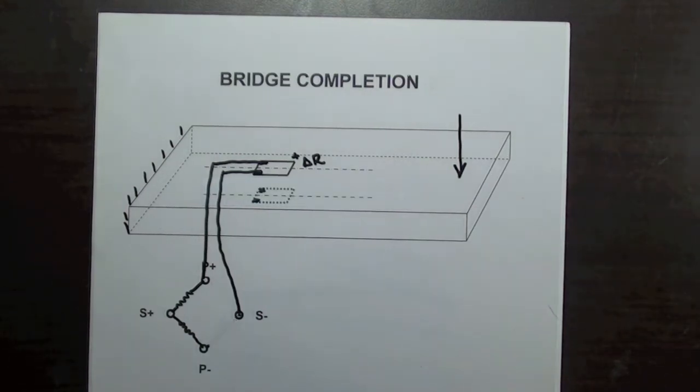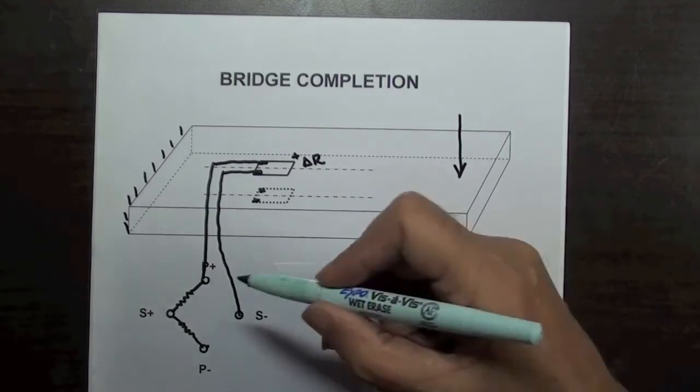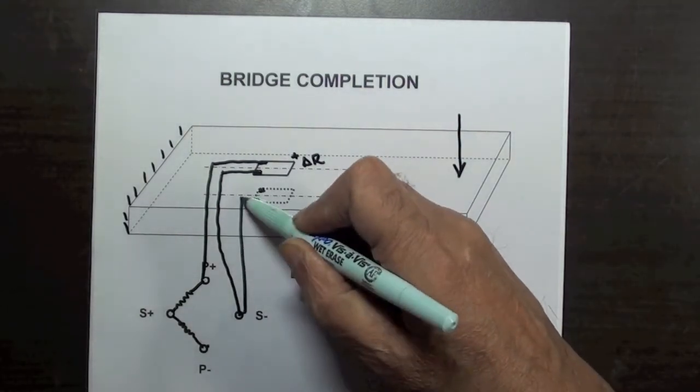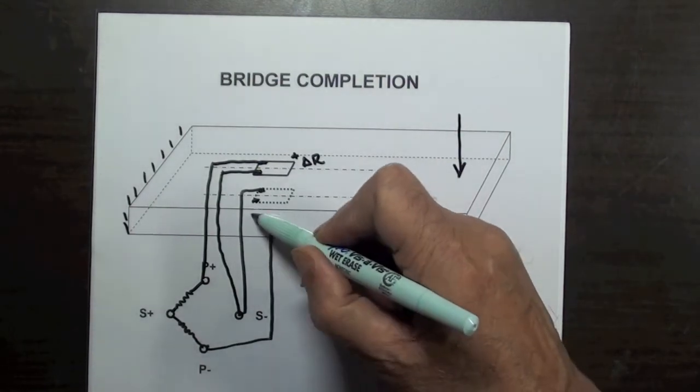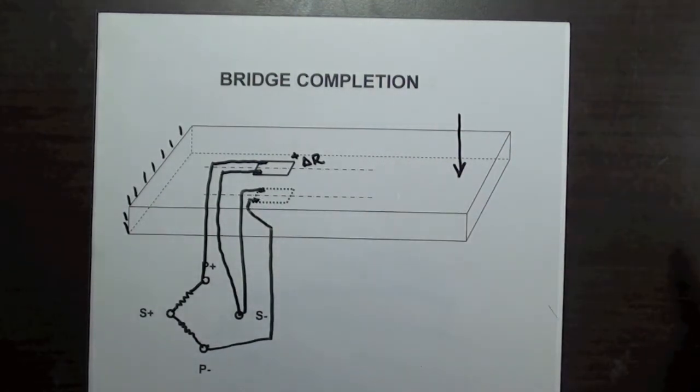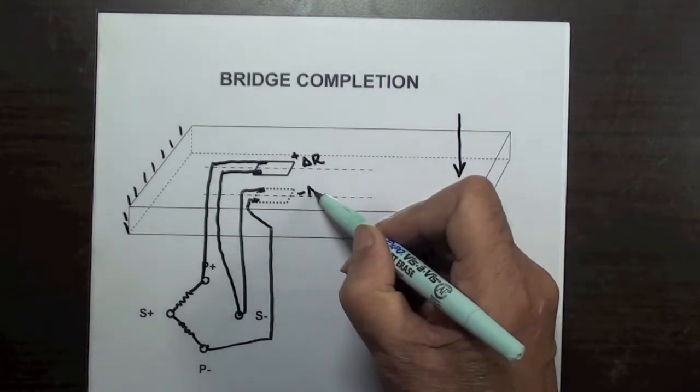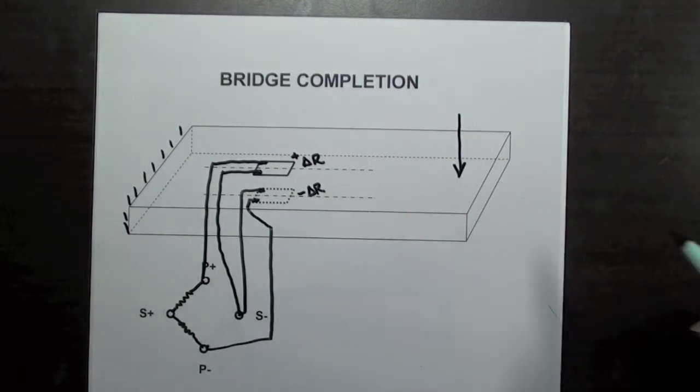On the same beam, if we have a second strain gauge bonded to the bottom surface at the same cross section, then the second gauge can be connected to the adjacent arm of the bridge. In this case, the bottom gauge will change resistance by minus delta R and the output of the bridge will be doubled.